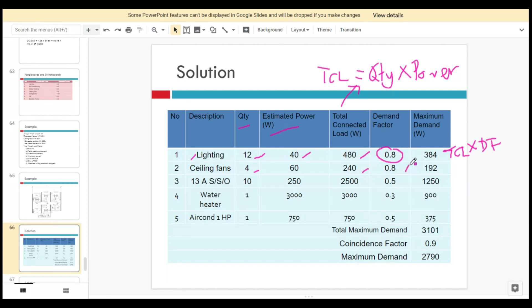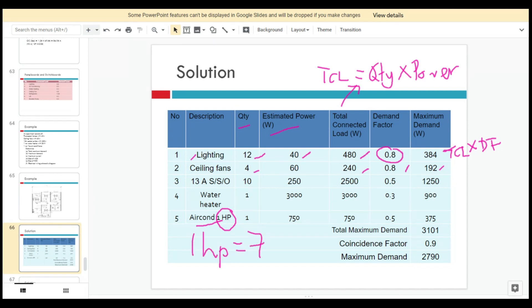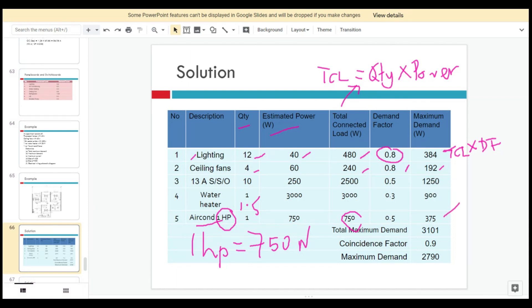For ceiling fans, 240 times 0.8 gives 192 watts maximum demand. For the air conditioner, one horsepower is equivalent to approximately 750 watts, so one times 750 watts gives 750 watts TCL. If it were 1.5 horsepower, you would multiply 1.5 times 750. Then multiply by the demand factor of 0.5 to get the maximum demand.